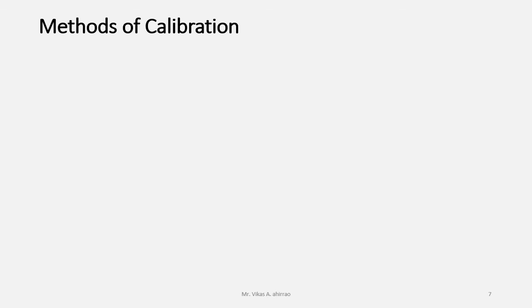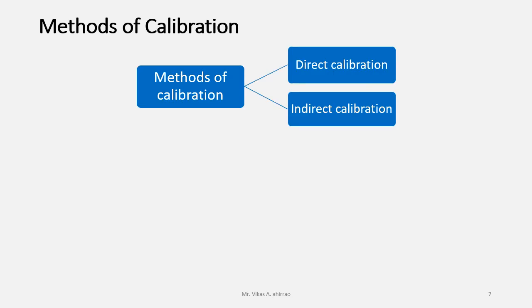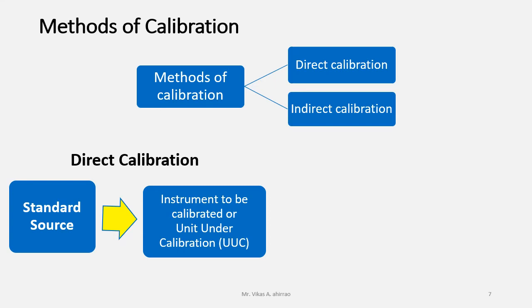Now we will go for the methods of calibration. Calibration methods are broadly direct calibration and indirect calibration. First, the direct calibration. In the direct calibration method, we will use a standard source whose uncertainty, accuracy, and errors present are known to us, and that standard source is used to calibrate the instrument or a unit under calibration.